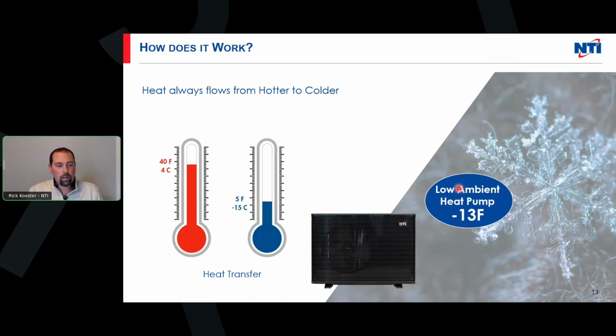But -13, and if you see somebody else with a -15 or a -20, we're all restricted on performance based on the refrigerant we're using. We have controls that may get us to different temperatures, but everything's restricted based on the refrigerant. As long as everybody's using R32, which is the case with most, if not all, heat pump manufacturers right now as far as air to water systems go, you have that limitation. When you're pulling that air through, what we're looking for is a large temperature difference. The larger it is, the more energy we can transfer at a quicker rate.